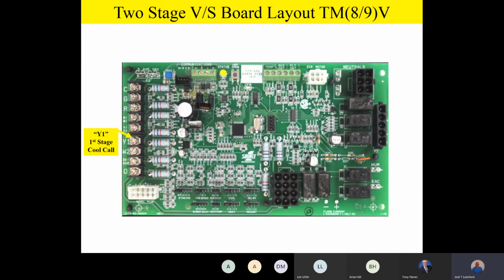So this is an important concept with ECM type of motors: they're sitting there, they've got power to them all the time, and then we drive or command it with 24-volt commands. It's no different on this. It's just that the board's doing more on a variable speed, because now on the board we're going to have some jumper selections where we can set airflow on the board instead of physically having to move a wire down onto the motor itself. Are there any questions or comments on that so far? Everybody good with that?